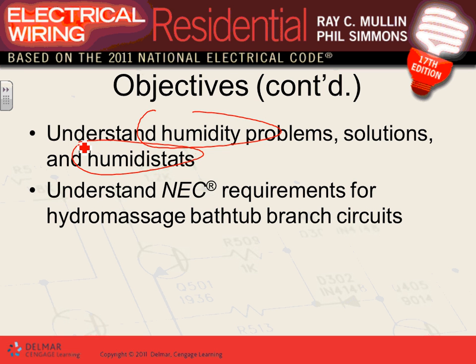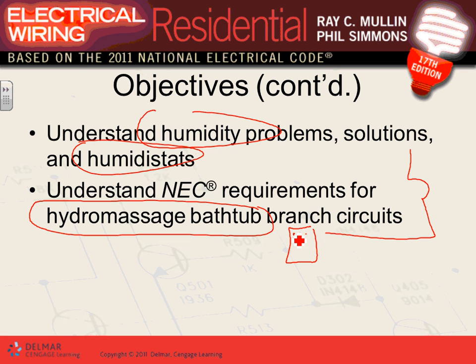Requirement for hydro massage bathtub, again, we'll talk about the GFCI requirement, plugs, and so forth. Hydro massage bathtub, very simple. You need a dedicated 20 amp branch circuit, landing on a GFCI receptacle that you plug the hydro massage bathtub pump into. Very simple. So I have my 20 amp circuit coming in to a GFCI receptacle, powering it. And then the hydro massage tub will be plugged into the GFCI, except the GFCI has to be accessible. So the way to make it accessible, guys, they have a GFCI trip right here, and they plug it into a regular receptacle. That's basically the only thing.